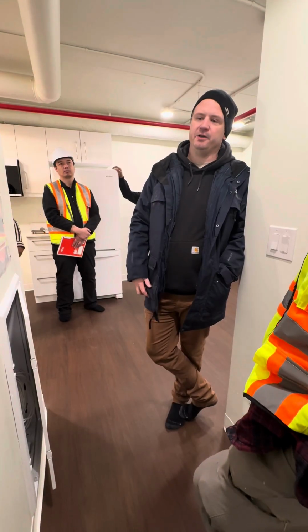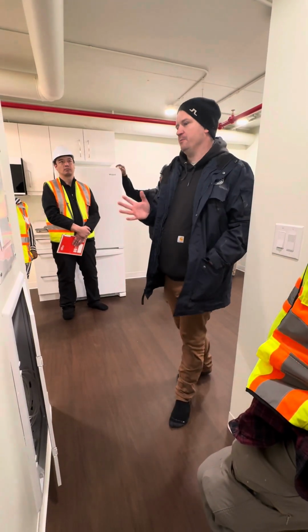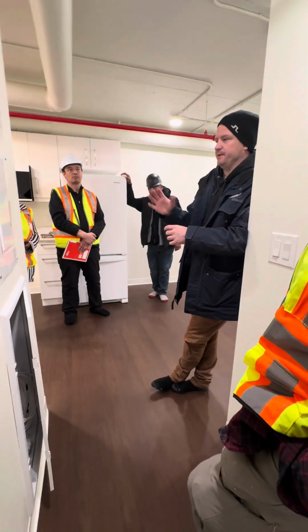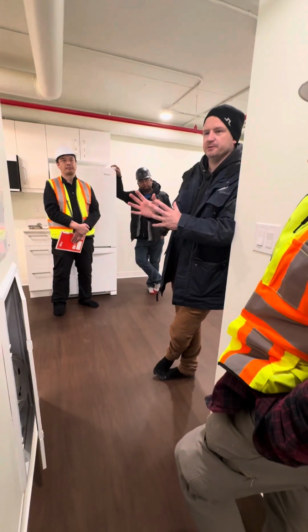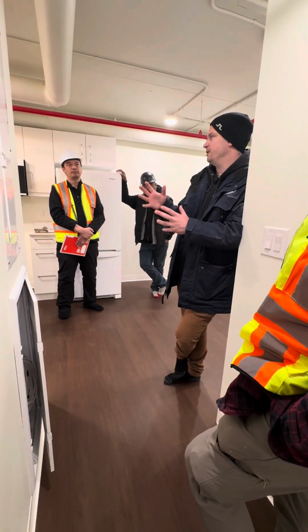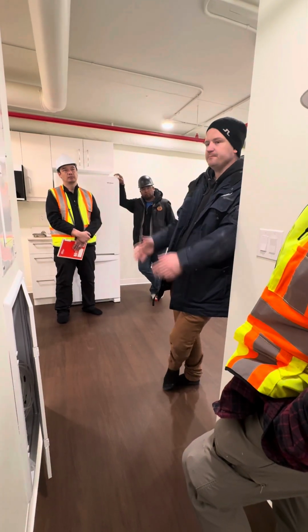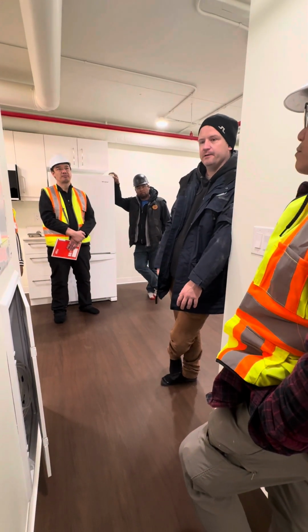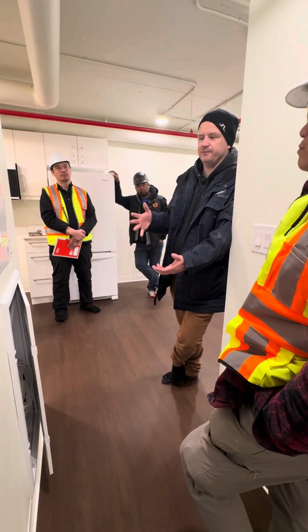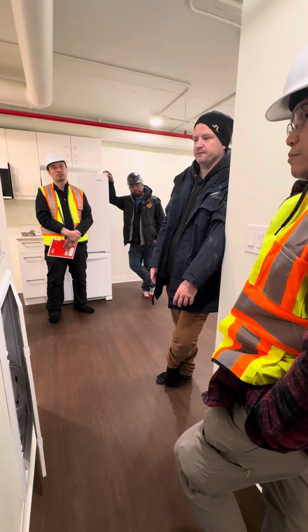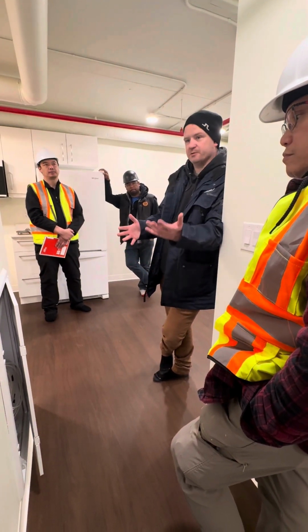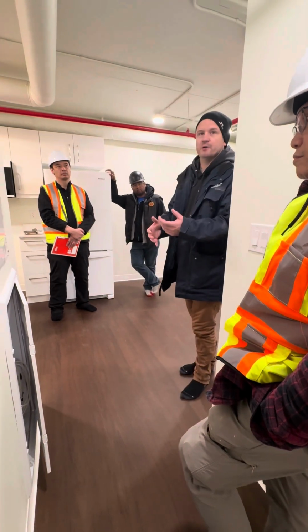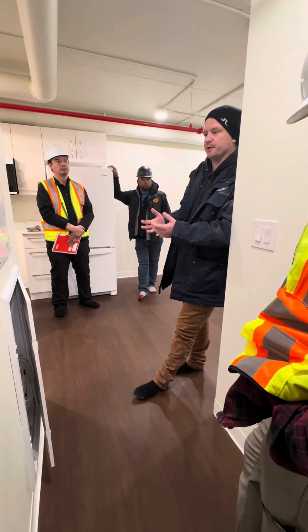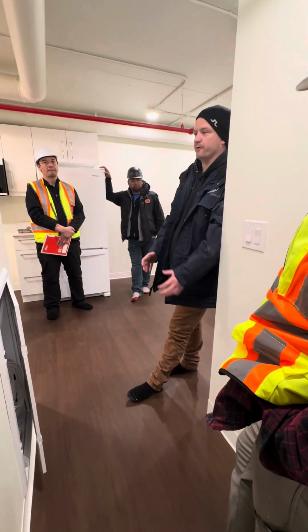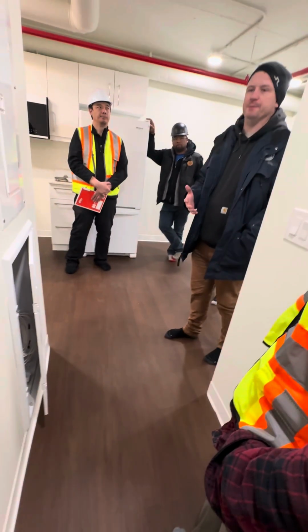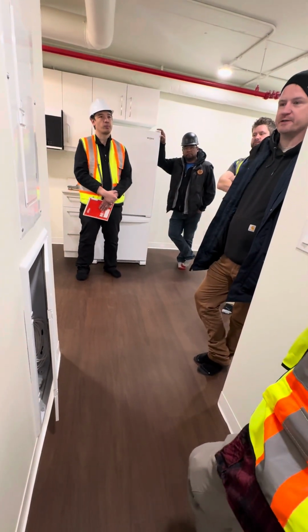But again, the best way of doing it, just for you guys, that we found in multifamily like this, where you're on a heat pump system, is let your tenants know, hey, we don't have cooling, just like a conventional building. We don't have cooling till May long weekend or whenever you guys decide to flip it over, and then run it that way. It can all be automated, and it is set up to be automated, so if you forget, but the best way to explain it to tenants usually is, yeah, it's 22 in here. It'll be opening windows or whatever to cool off. There's no mechanical cooling until May 11th or whatever it is, or the entire building needs cooling. And then it'll give you a step-by-step procedure on how to fix it or what to look at, things like that.